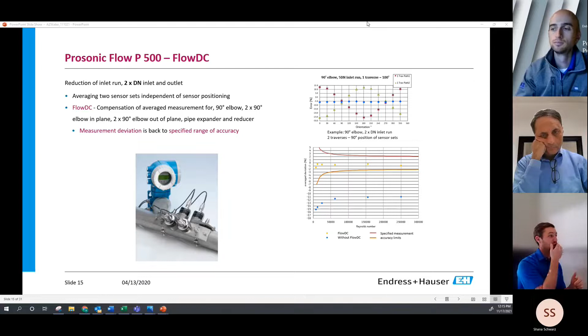And effectively what we're doing is averaging the 2 sensor sets independent of the sensor positioning. So when you think about a clamp-on flow meter, you can do direct signal passing back and forth. You can do the reflect mode, as you see in this photo here, and it gives you the flexibility, based off your retrofit or installation, to set up those transducers how you want. The firmware is called Flow DC, and it's compensation of average measurement for different use cases. Again, the 90-degree elbows, pipe expanders, reducers, and the like. And the measurement deviation is back to the specified range of accuracy. So effectively we're taking any of these uncertainties and bringing them right back into the measurement error that we're looking for.